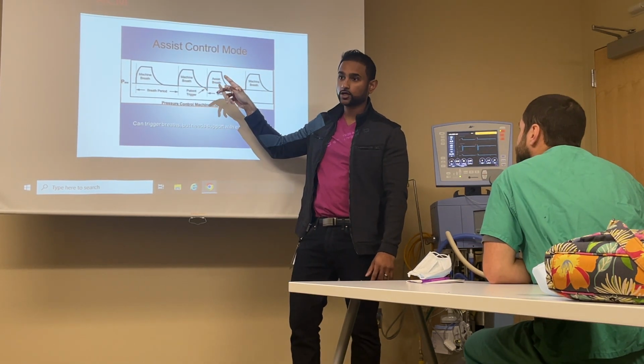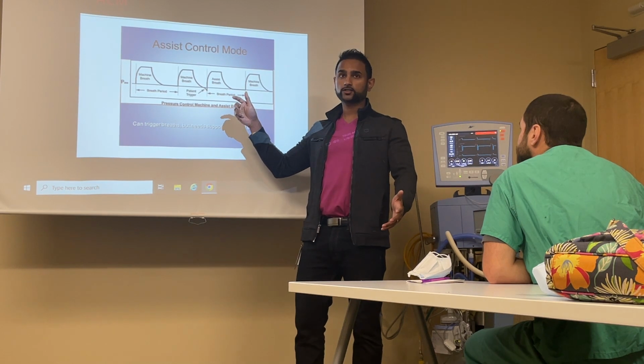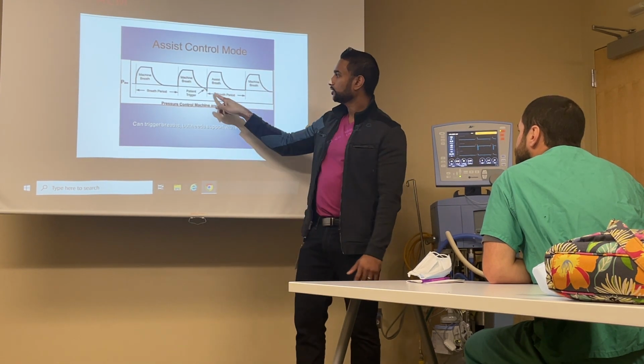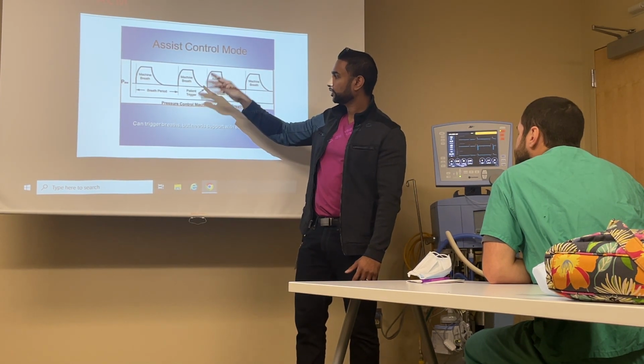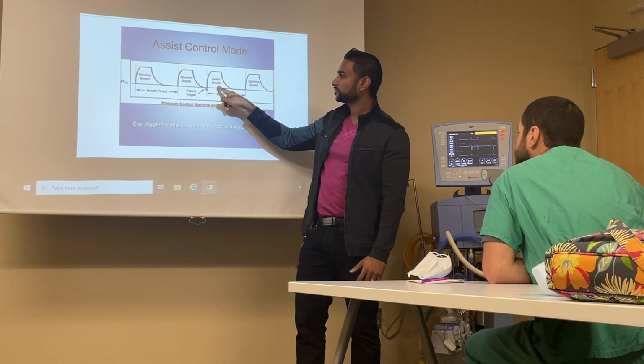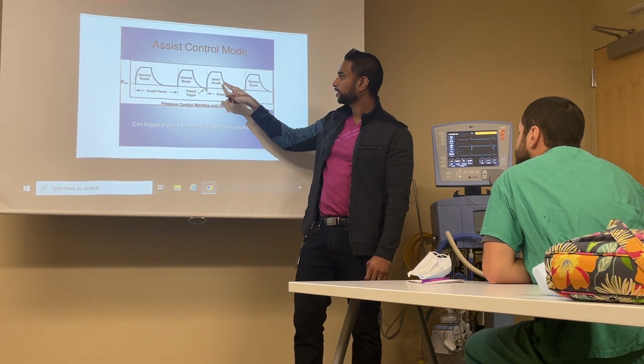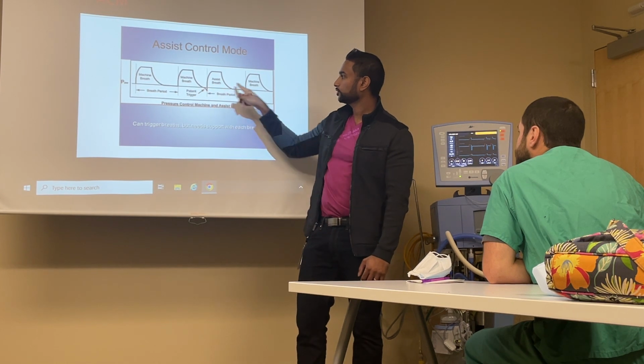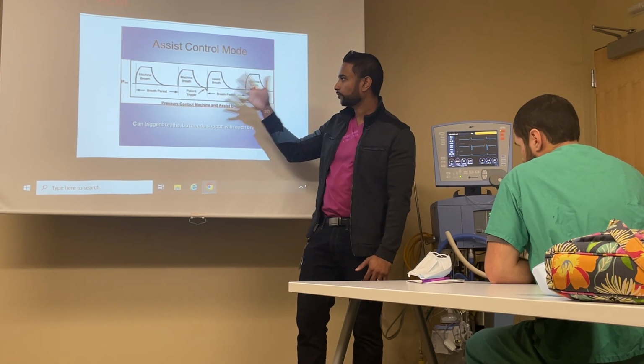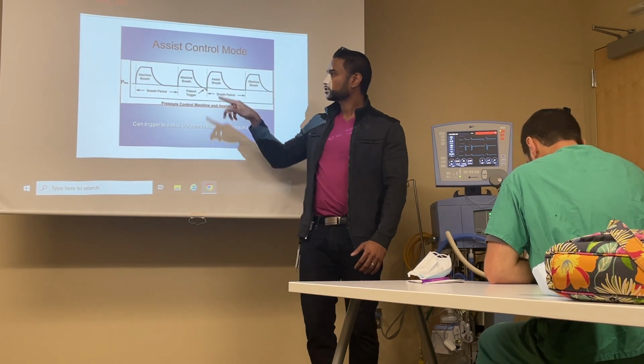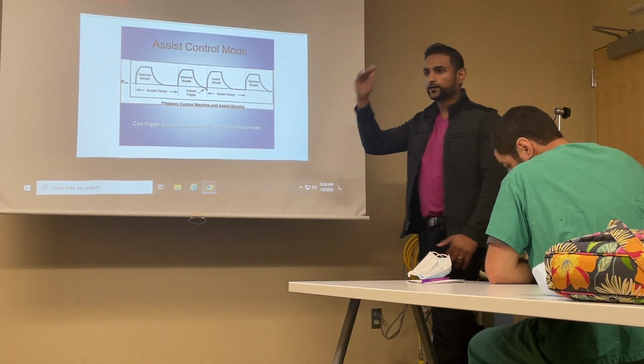Patient triggered another breath. And guess what? Machine said, oh, I sense a trigger. Here's a 500 cc volume. Before it can completely come to an exhalation phase, another breath kicks in. This is called the assisted breath, which is the patient's breath. And all of a sudden, the time cycle to stimulate another breath from the machine has already reached that point, another breath is coming. So the volume never changes, 500, 500, 500, 500.